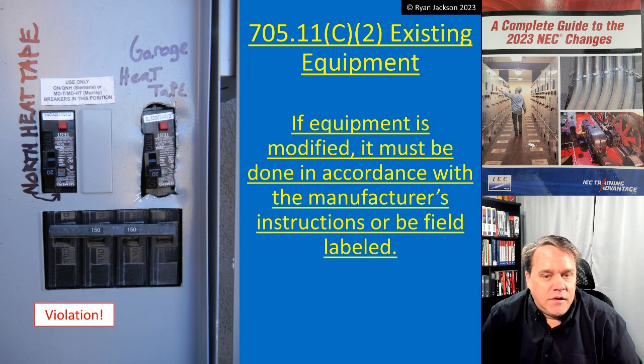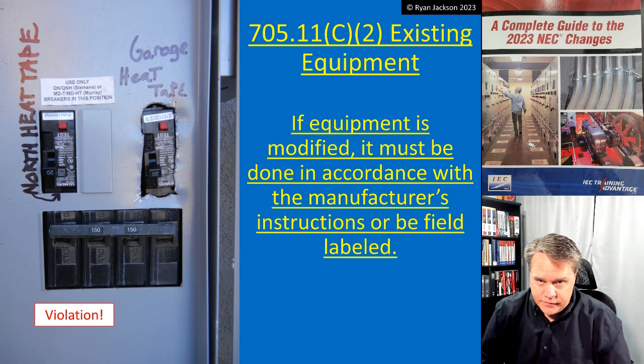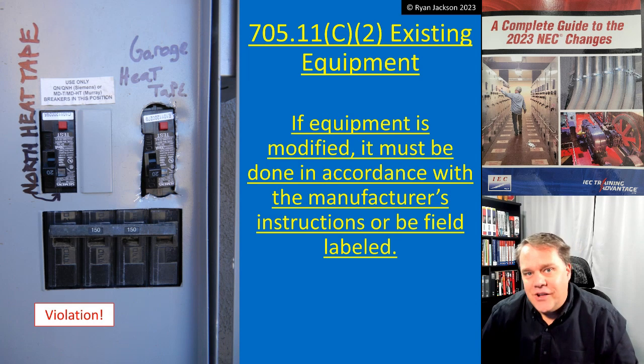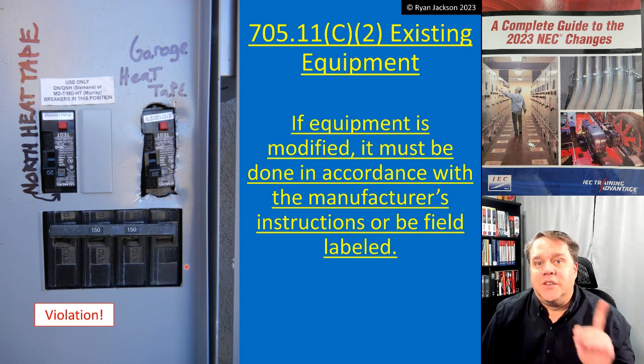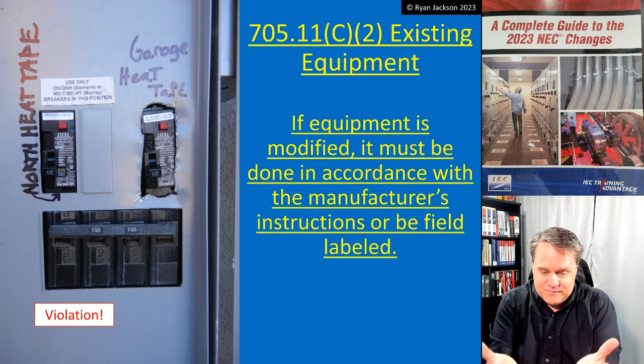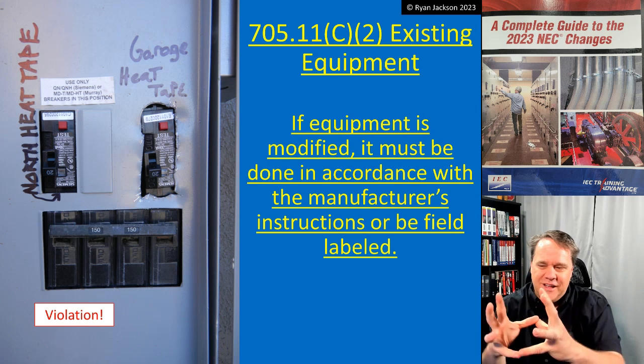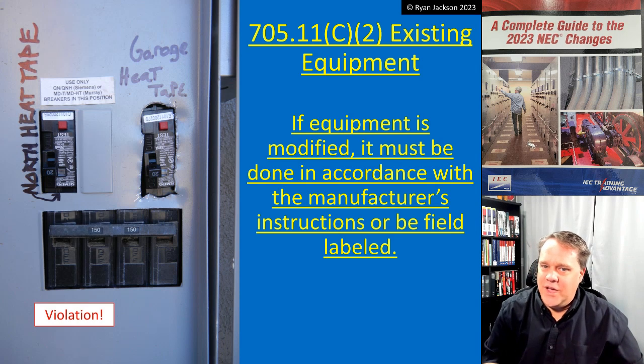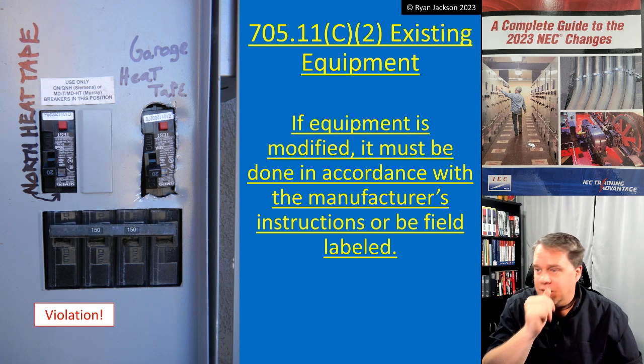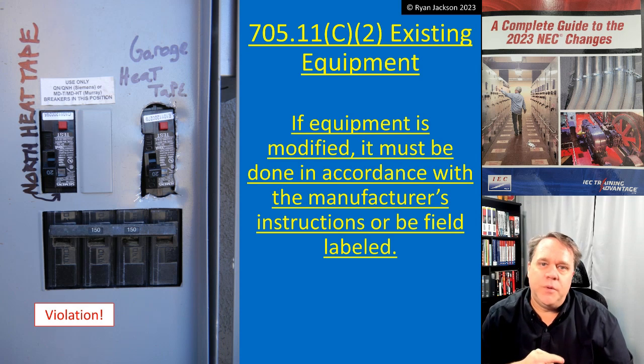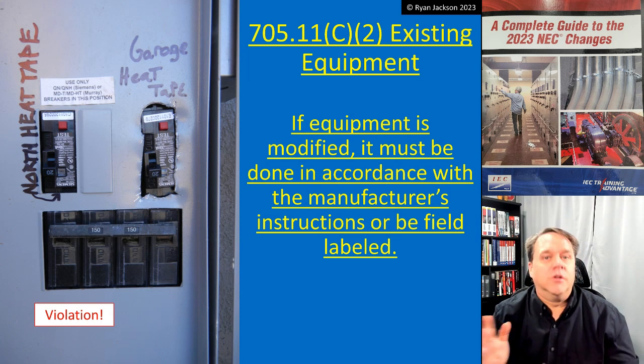If the service equipment is modified, it must be done in accordance with the manufacturer's instructions or be field labeled. Sometimes people get way too creative — for example, you can't just sawzall a new hole in a panel for your circuit breaker. Specialty inspectors are going to see a lot of this, especially with solar, because people try to fit existing equipment into new installations. If you have no instructions and you're modifying the equipment, you'll need to call a field evaluation body — like UL, Intertek, QPS, or TÜV — have them do a field evaluation, and if they sign off, they'll issue a field label and field evaluation report.